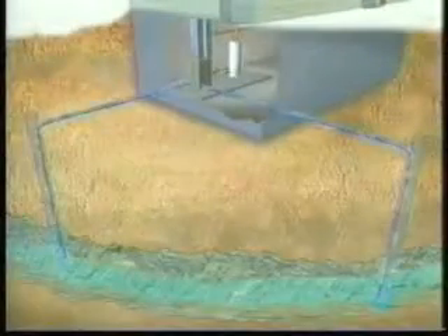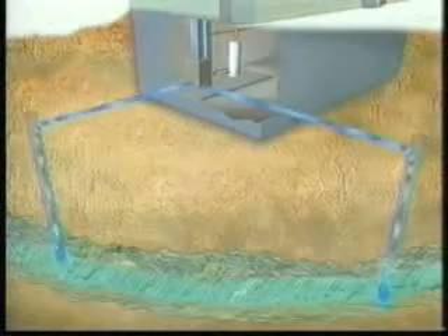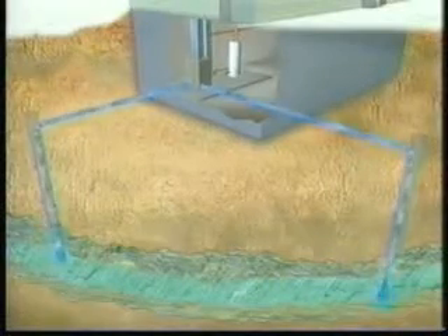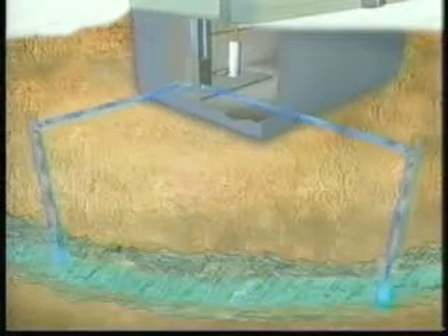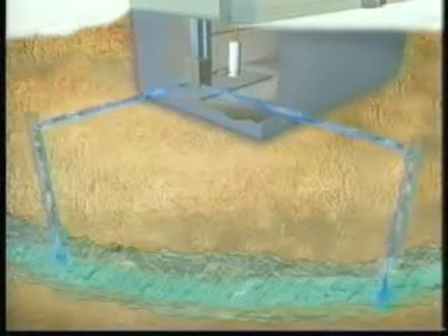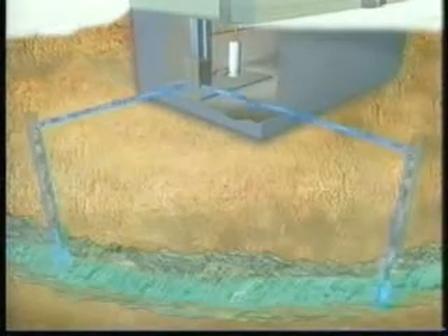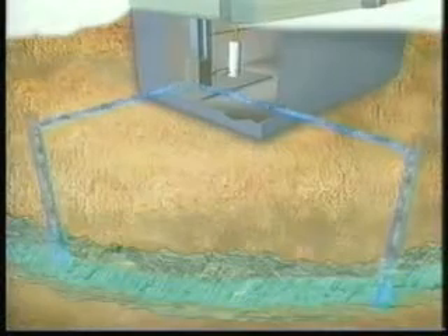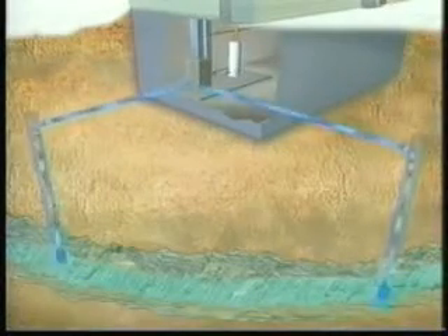In an open loop system, on the other hand, groundwater from an aquifer is pumped through one well and passes through the heat pump, where heat is added to or extracted from it. The water is then discharged back to an aquifer or harnessed for other water management uses. Because the system's water supply and discharge are not connected underground, the loop is open.